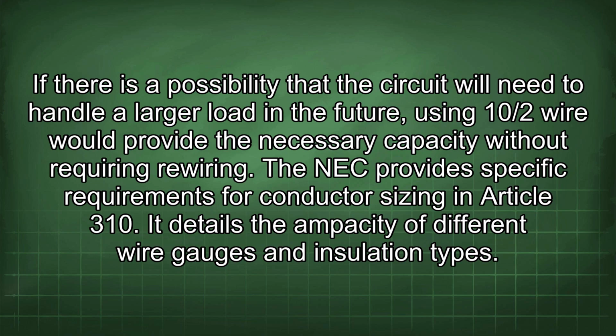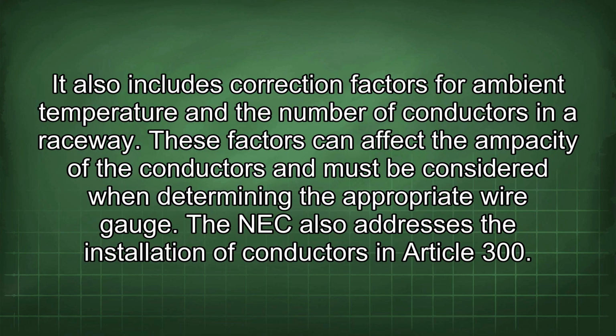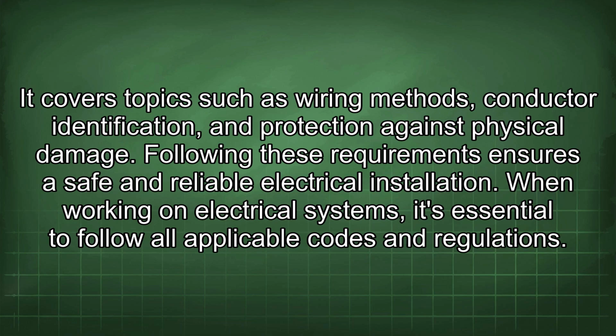The NEC provides specific requirements for conductor sizing in Article 310. It details the ampacity of different wire gauges and insulation types. It also includes correction factors for ambient temperature and the number of conductors in a raceway. These factors can affect the ampacity of the conductors and must be considered when determining the appropriate wire gauge. The NEC also addresses the installation of conductors in Article 300. It covers topics such as wiring methods, conductor identification, and protection against physical damage. Following these requirements ensures a safe and reliable electrical installation.